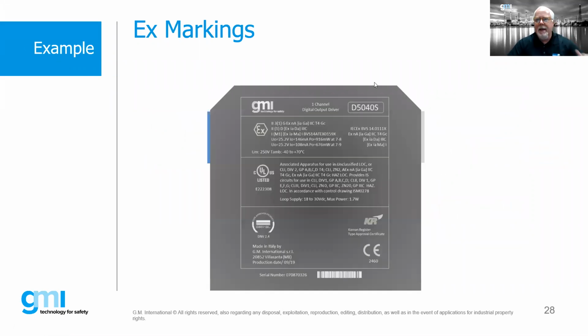So using the example from GMI on a barrier, what we actually see here, this line, what you notice is that we have a Roman numeral 2, 3, and we also have a 1 in parentheses. So what this is telling us, with our EX here and our CE mark and our Roman numeral 2, and category, is that it has ATEX. And by the way, there's our little ATEX giveaway. But now we have this 1 in brackets and we have 3 here.